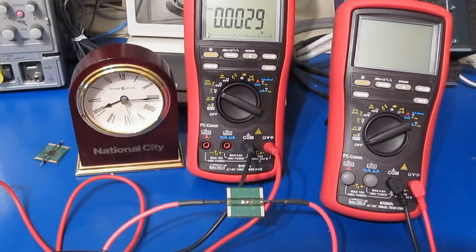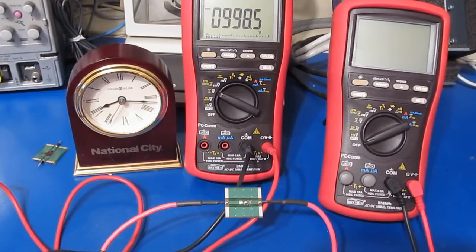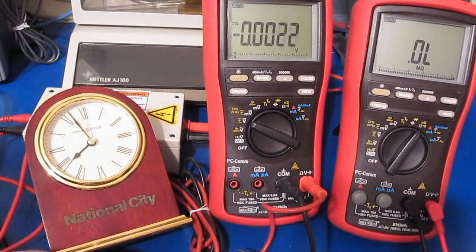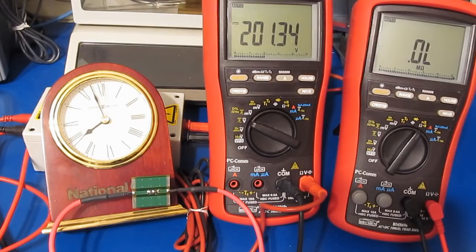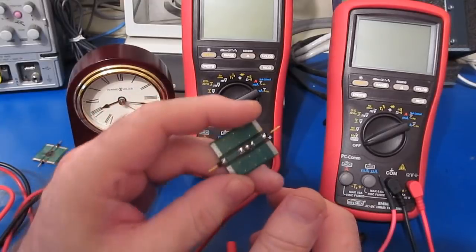All right, let's try this again with our two resistors in series. So here's a thousand volts, no problems. Let's just try putting two thousand volts across this and have to turn it up a little bit. And there you have it, so that's two thousand volts for one minute.